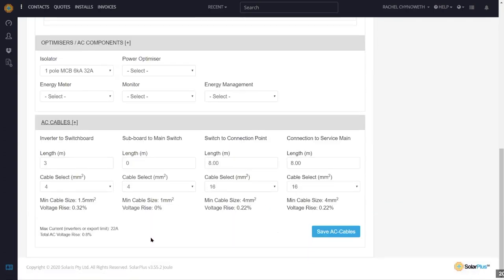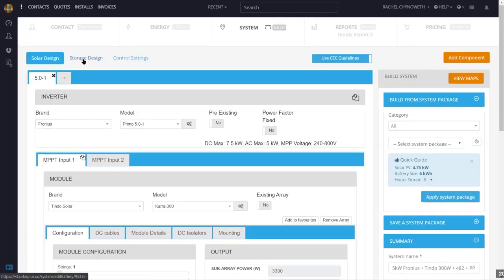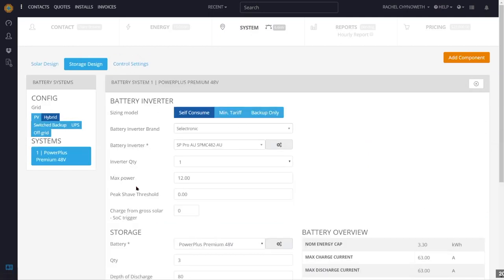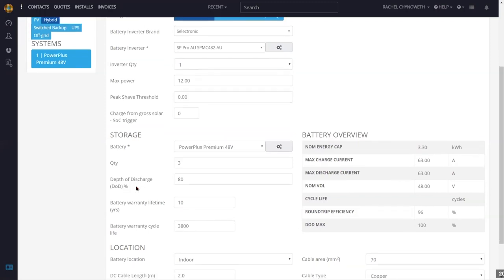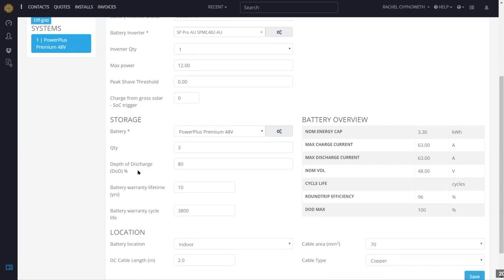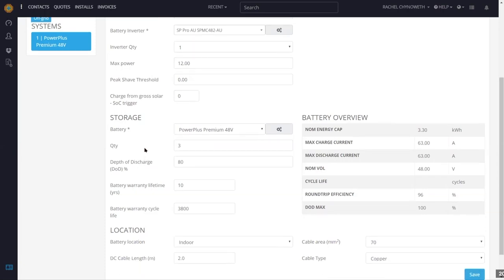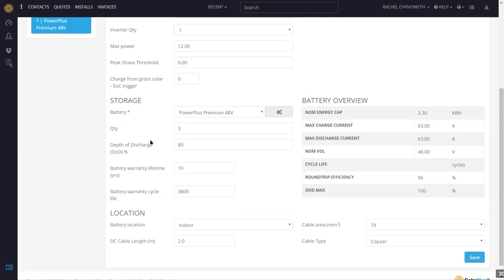We have AC voltage rise calculations that go from the solar inverter all the way to the point of common coupling. If you enter your lengths and cable size, it will calculate your total AC voltage rise. Moving to the battery page — this is a system package where I've entered battery information. I've added an inverter and some batteries. These are lithium batteries, so Solar Plus knows to place them in parallel. If you selected lead acid, it would know they're in series.